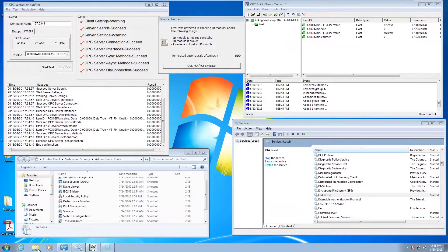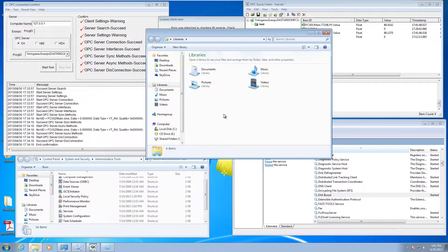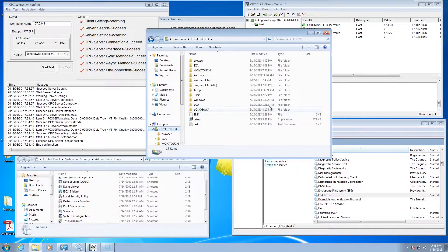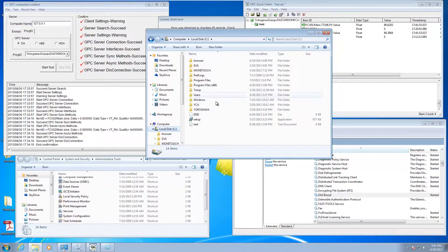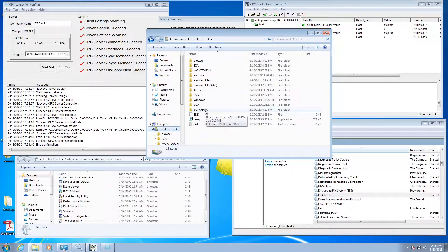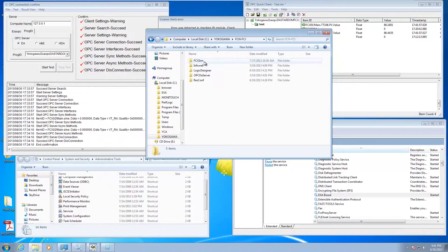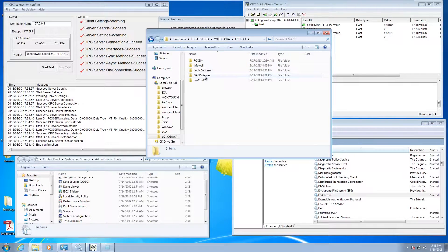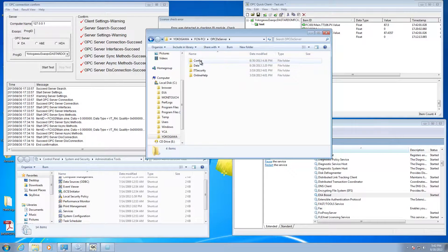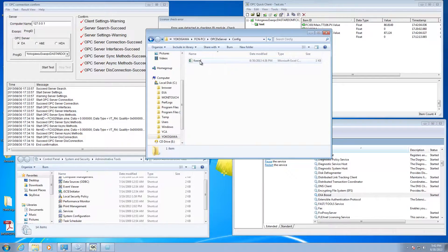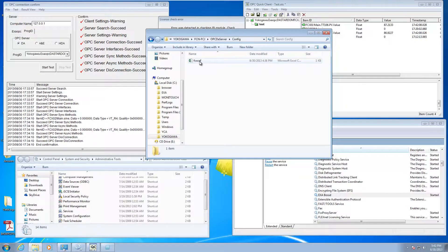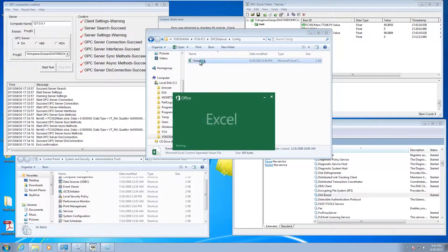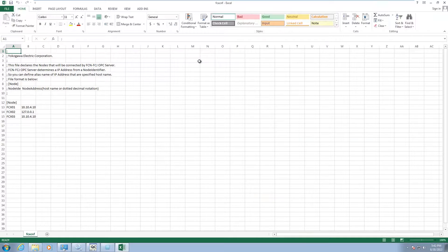What the manual is going to tell you to do is browse to where the OPC server is installed. By default, it goes to the Yokogawa directory on the C drive under FCN FCJ OPC DA server. There's going to be a folder called config. In that folder, there's a comma separated file called FCX CNF.